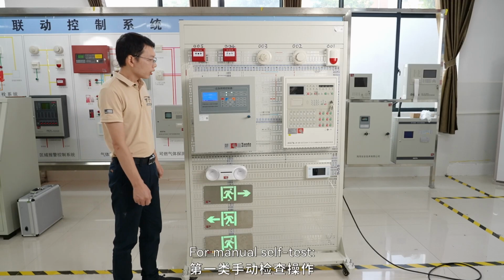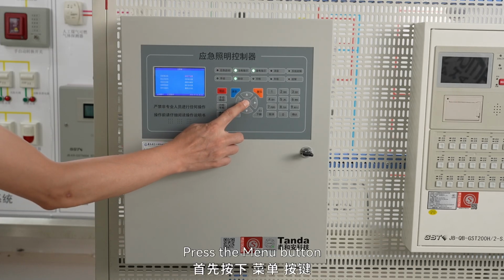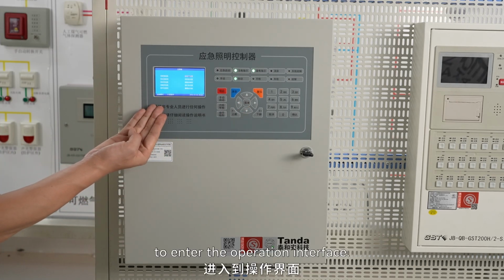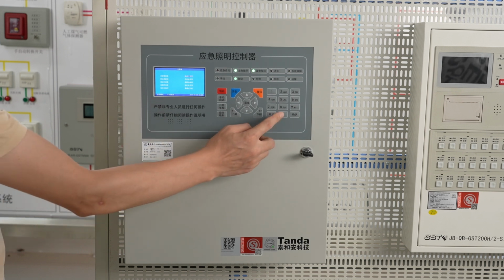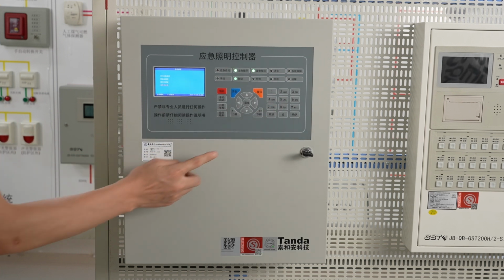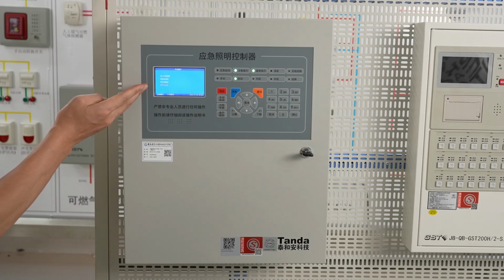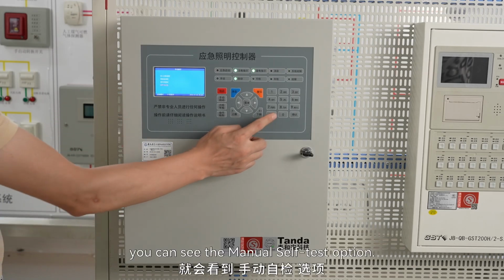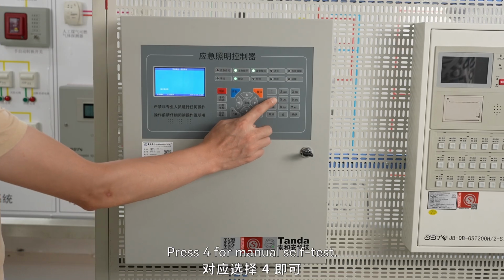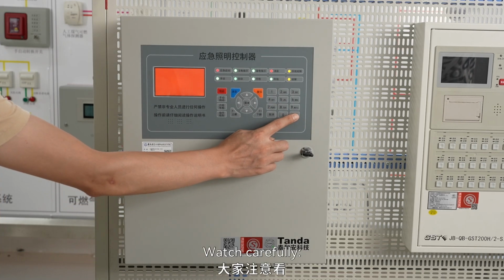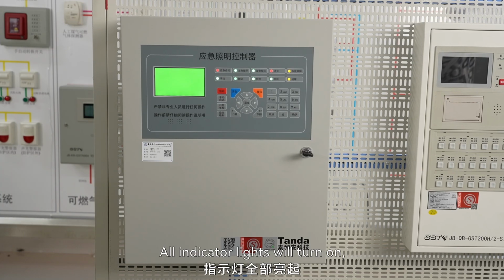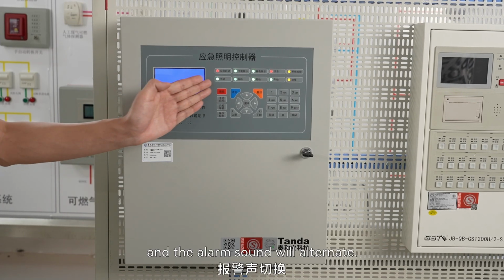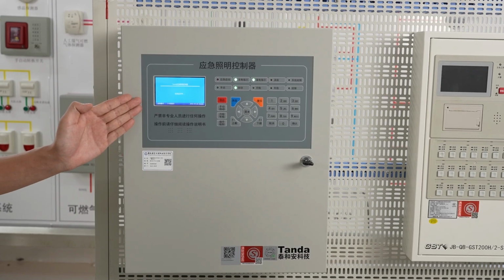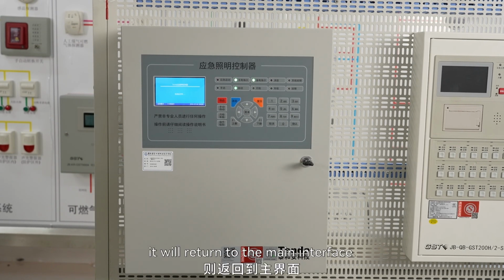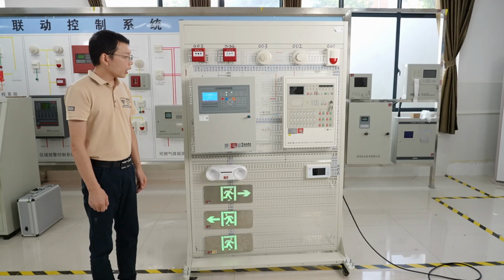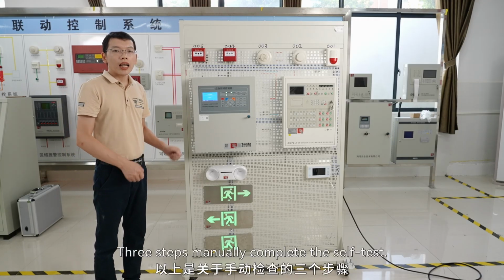For manual self-test, press the menu button to enter the operation interface. Select 5 Manual Operation. At this point, you can see the manual self-test option. Press 4 for manual self-test. Watch carefully. All indicator lights will turn on, the display will flicker, and the alarm sound will alternate. If everything is normal, it will return to the main interface. 3 steps manually complete the self-test.